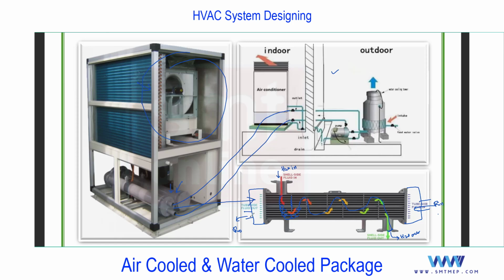Here we are cooling the refrigerant by using water instead of air. What we discussed in the vapor compression cycle: if you use air to cool the condenser, that is called an air cooled system. If you use water to cool the condenser, that system we call a water cooled system. Here we are talking about packages, so this is the water cooled package. We are using water to cool the refrigerant. But again, in order to reuse this water, the water must reject the heat, because it's a cycle, right? So what will happen?